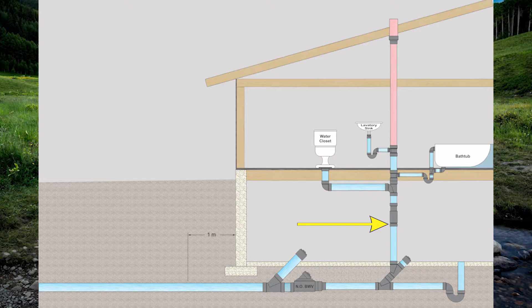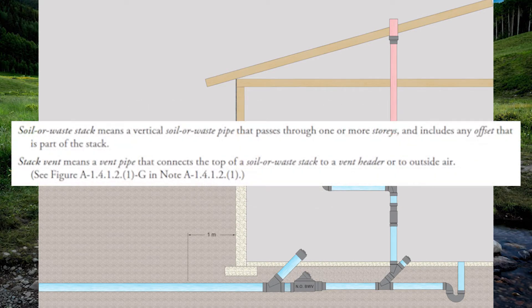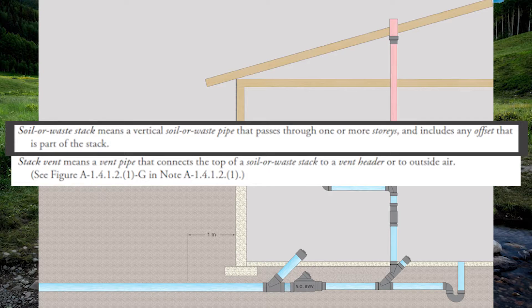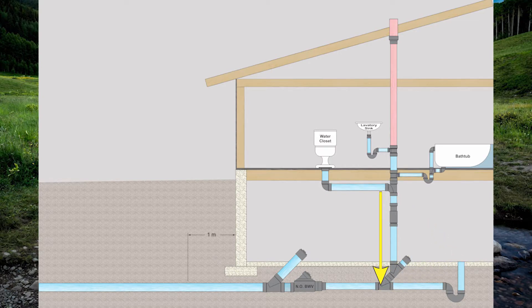Now let's head back to that main stack. Main stack is a trade name — its official name is a soil or waste stack, which I just call a sow stack. The code definition: soil or waste stack means a vertical soil or waste pipe that passes through one or more stories and includes any offset that is part of the stack. A soil or waste pipe is a sewage pipe. So our lav sink upstairs drains into the stack, goes all the way down through one story, and drains into the building drain — making this a soil or waste stack.